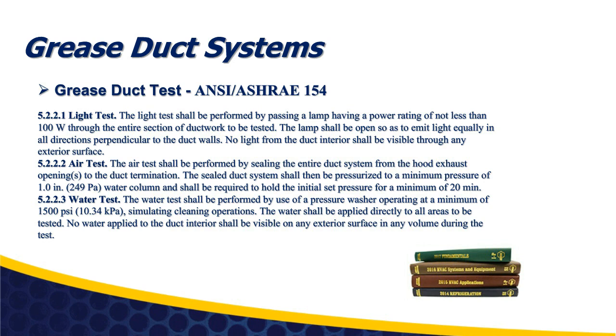Now, the last test listed in ASHRAE 154 would be a water test, where you basically go through and simulate cleaning operations with a minimum of 1,500 psi pressure, spraying the entire system down to simulate a cleaning operation, to make sure that all the joints, access points, you name it, will not leak water out, to ensure that they are leak-free.